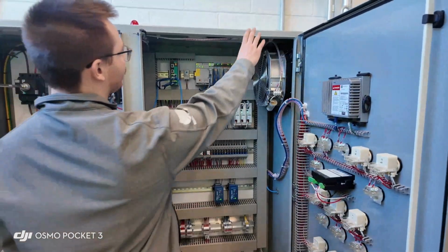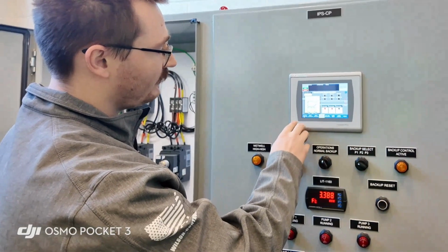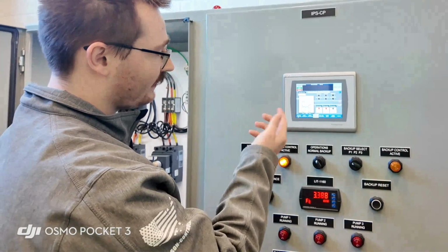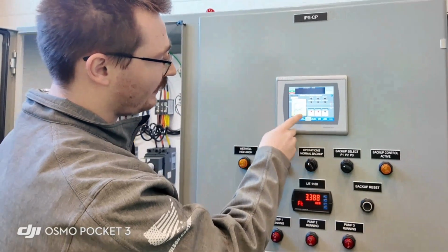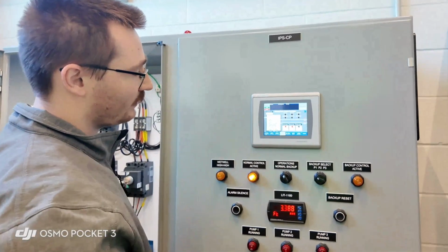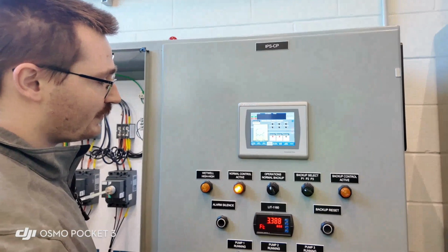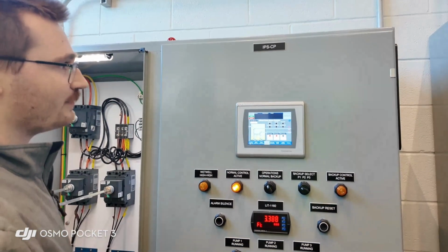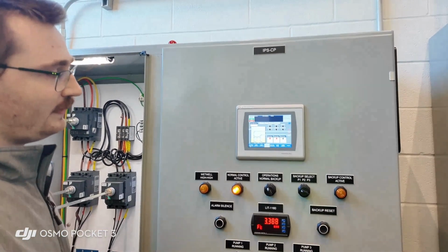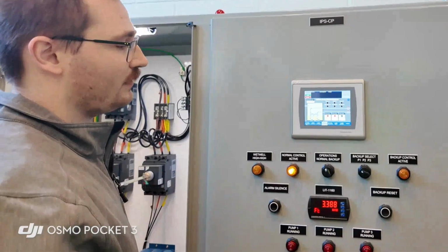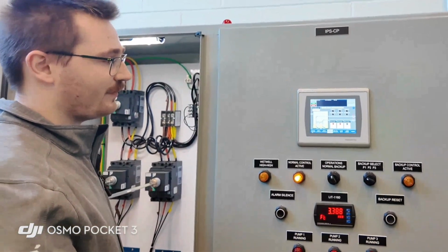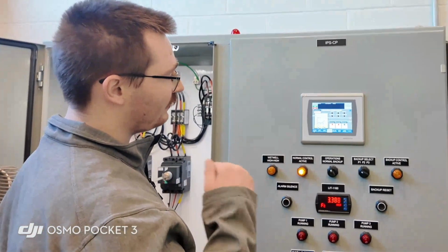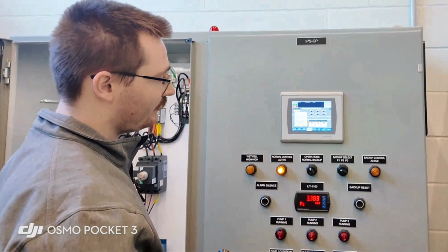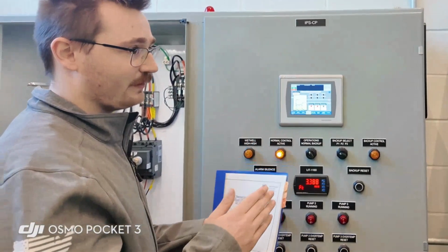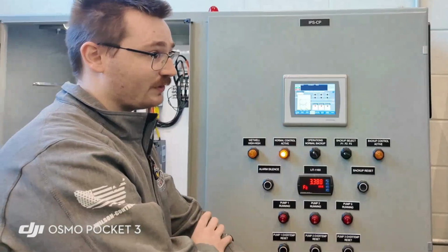So you have your well, and you have your 2 pumps, and you just get your well level, and this will actually go up with the level of the well. The transducer we provided is ranged from 0 to 10 foot, and it was mounted with a 9-inch offset. So we have it scaled from 0.8 to 10.8 feet. You want to keep it within that window when you're changing set points, like level control.